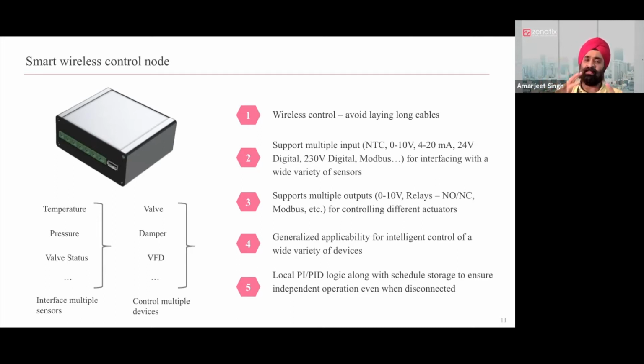And this wireless PLC or DDC can then be connected back to the gateway, right? Few things which are really nice about this control card versus, let's say, a DDC. One, it's completely wireless, right? So even in an existing building, you go to an AHU room, you simply install this. You don't need to lay out cables to connect this back to the gateway. It will wirelessly connect back to the gateway. Because it's a powered device, in addition to performing its own function, it will also act like a routing node for the rest of the wireless mesh. So it adds to the overall resiliency of the wireless mesh that you are creating within the building, right?